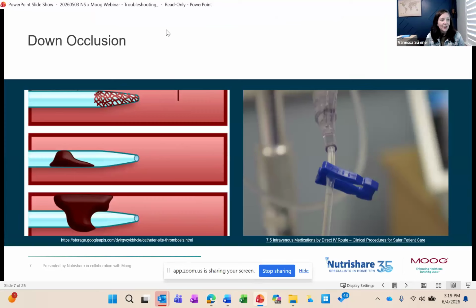So another alarm you've probably seen is the down occlusion alarm. This means the pump is sensing excess pressure in the line between the patient and the pump. Now remember, there will always be some pressure in the patient's tubing. So if your pump has a pressure line reading, as long as there are no alarms, you should be okay. You should have some pressure. But this alarm can occur for many reasons. We're looking for a problem downstream, so from the pump down to the patient. And this can even be in the patient's catheter.